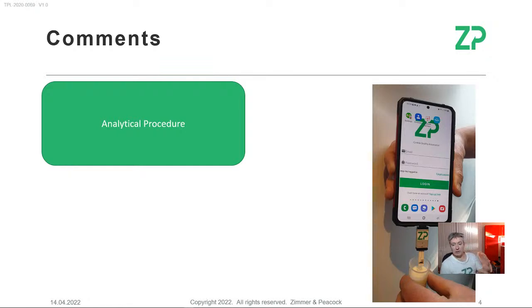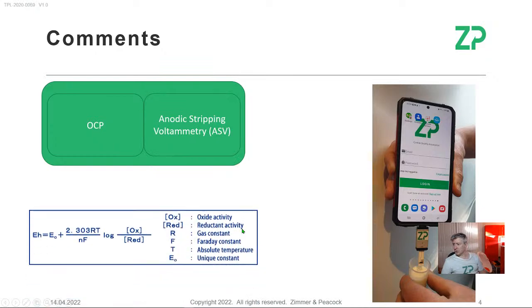But I was asked the question, how do you measure iron 2+ in water? And I think there's an overall analytical procedure, but within that, one of the first things that you would do is measure open circuit potential, and then you would potentially do anodic stripping voltammetry. So the reason I bring up open circuit potential is because the question had a very specific, it said Fe2+. I want to measure iron 2+. So that tells me one of the first things you could do is measure the open circuit potential, and small USB powered potentiostats can do that these days. You have the voltage, and by measuring the voltage, you're actually measuring the ratio between the oxidized species and the reduced species.